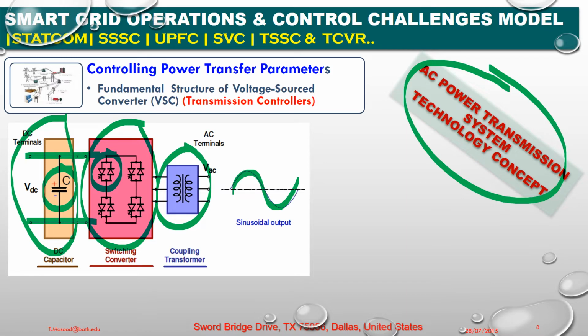So the DC current can flow in either direction, and it can exchange DC power with the connected DC system in either direction. The AC side is a generated AC voltage connected to the AC system, as we have seen demonstrated here. The AC voltage source with low internal impedance, with a series inductive interface to the AC system, usually through a series inductor or a coupling transformer as we demonstrated, is essential to ensure that the DC capacitor is not short circuited and does not discharge rapidly into a capacitive load such as a transmission line.